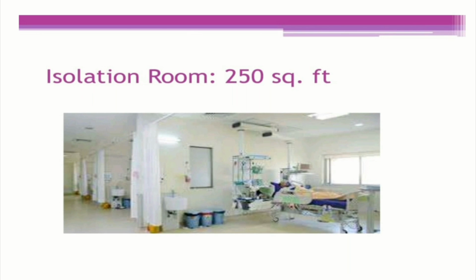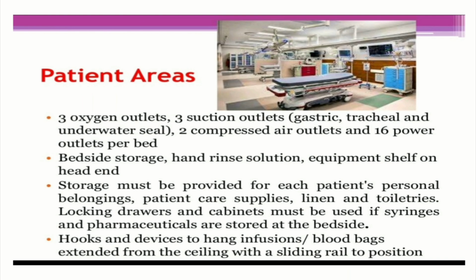Isolation room is 250 square feet. Patient areas: 3 oxygen outlets, 3 suction outlets, that is gastric, tracheal, and underwater seal, 2 compressed air outlets, and 16 power outlets per bed. Bedside storage, hand rinse solution, equipment shelf at the head end.